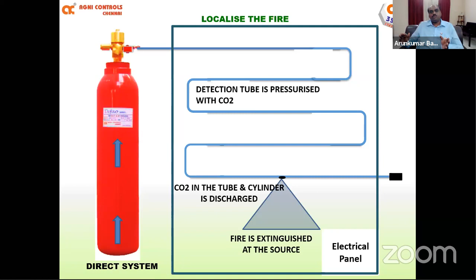In this method, we use the detection tube both as a detector and, once it detects and bursts, as a nozzle. This is the direct method, and because it is direct, we cannot use it beyond a certain cubic meter. The next method is the indirect method, which is the detection and actuate method.